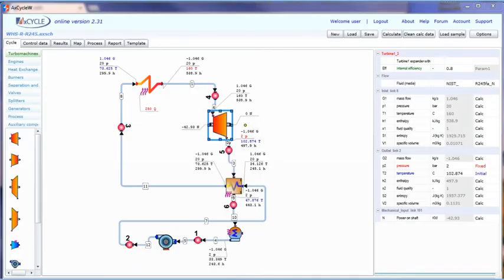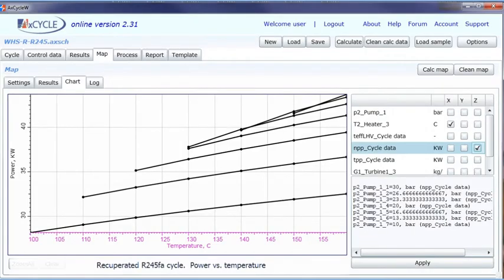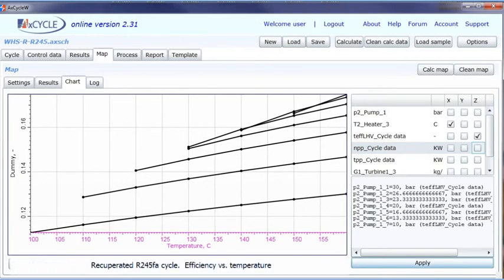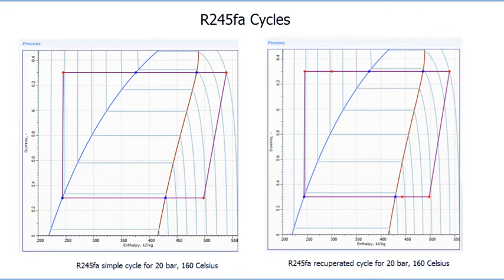The recuperated waste heat recovery Rankine cycle with R245fa as working fluid is shown for an operation point of 20 bar, 160 Celsius. The output flow after the turbine is about 102 Celsius, allowing use of a recuperator to heat the liquid after the pump from 34 up to 74 Celsius. The recuperated R245fa cycle power versus temperature and efficiency versus temperature plots are shown, along with contours of power versus temperature and pressure defining the operational range. A comparison of processes for simple and recuperated R245fa cycles is also presented.